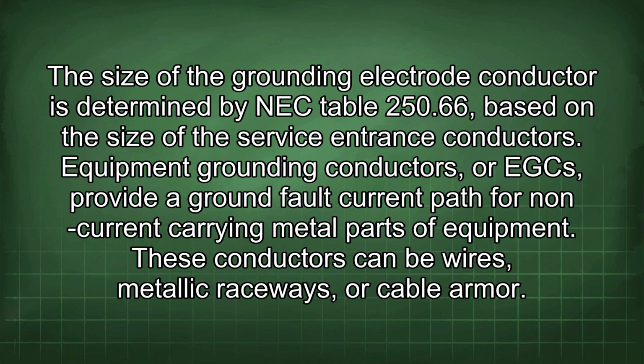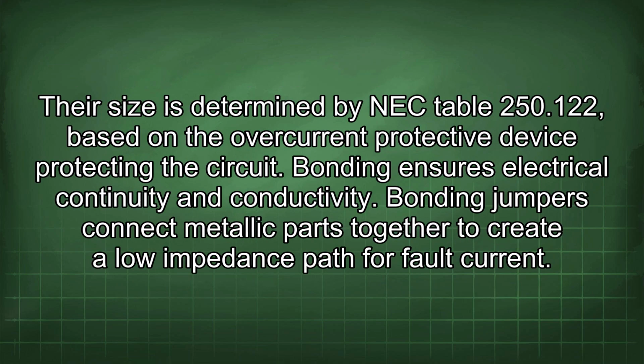The size of the grounding electrode conductor is determined by NEC Table 250.66, based on the size of the service entrance conductors. Equipment grounding conductors, or EGCs, provide a ground fault current path for non-current carrying metal parts of equipment. These conductors can be wires, metallic raceways, or cable armor. Their size is determined by NEC Table 250.122, based on the overcurrent protective device protecting the circuit.